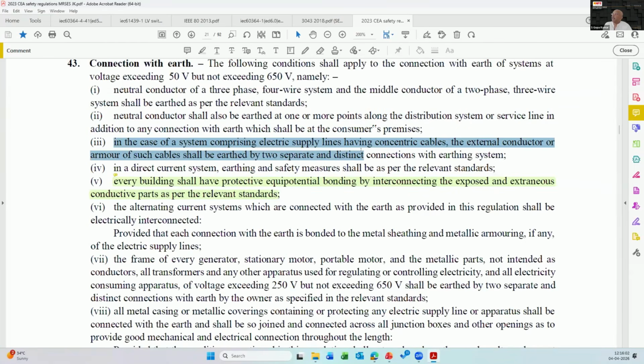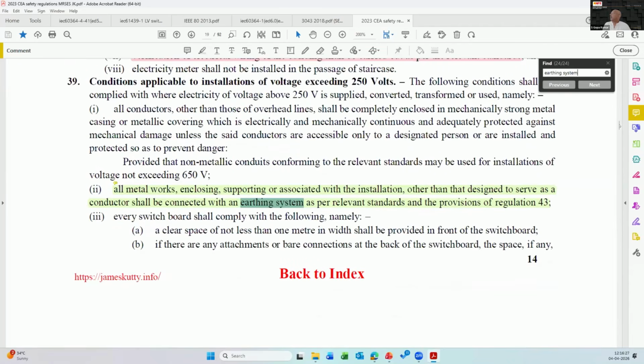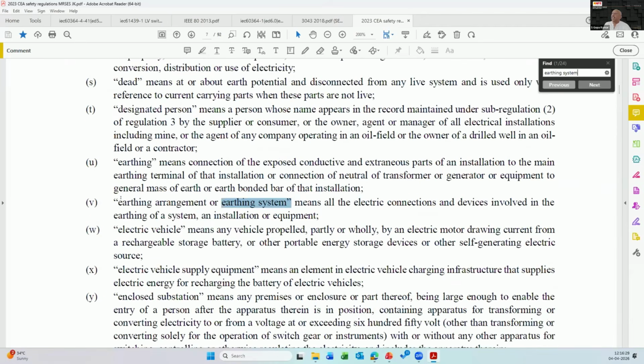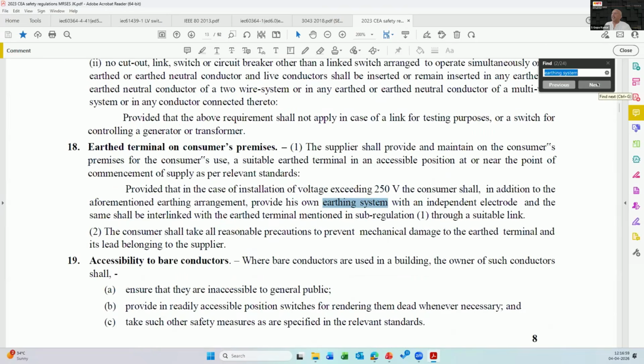In case of a system comprising an electric supply line having concentric cable, the external conductor or the armor of such cable shall be earthed by two separate and distinct connections with the earthing system. Please note that there is a definition for earthing system. Let me show you the definition of earthing system first, then I will take you through this explanation. The definition of earthing arrangement or earthing system is, it is not about earth pit or earth electrode. Earthing system means all electric connections and devices involved in the earthing of a system, an installation or equipment. All the connections, all the bus bars, wires, connections, all together is called the earthing system. Earth electrode is one of the components in the earthing system.